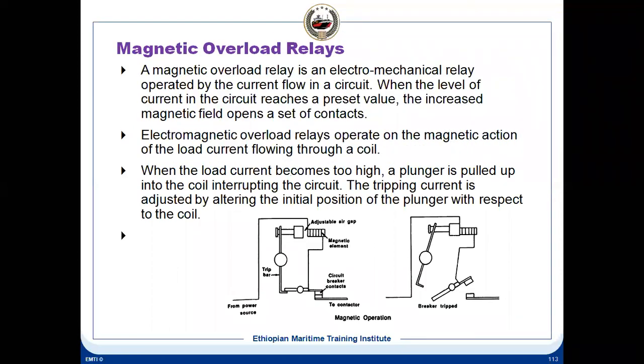A magnetic overload relay is an electromechanical relay operated by the current flow in the circuit. When the level of current in the circuit reaches a preset value, the increased magnetic field opens a set of contacts. You can see here, this will operate this. This is a coil here. When it operates, this will cut off the power. When it opens this, the power is connected here. This is the control supply. Normally you'll find these control coils are 220 volt or 110 volt. Mostly 110 or 220; 24 volt you won't find.